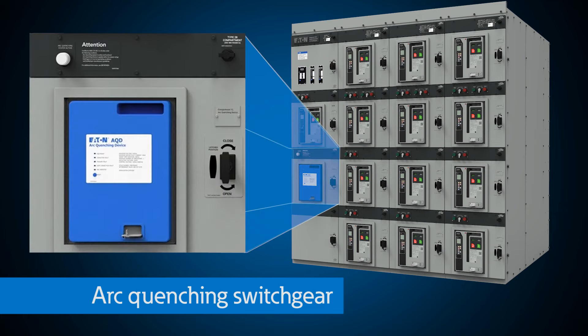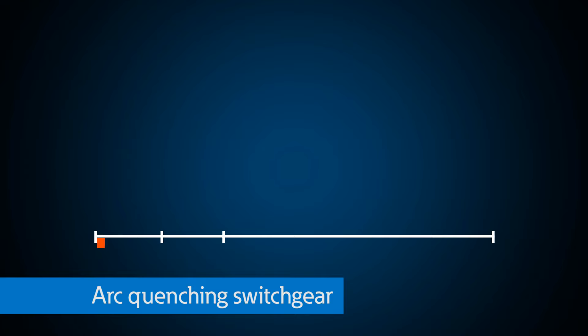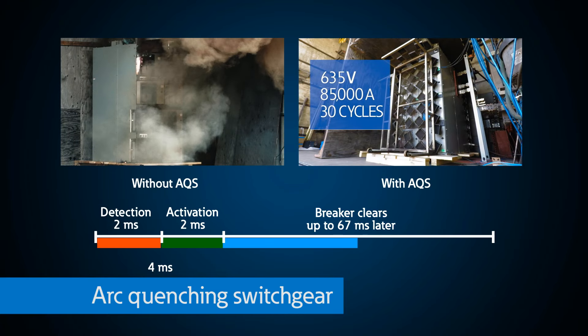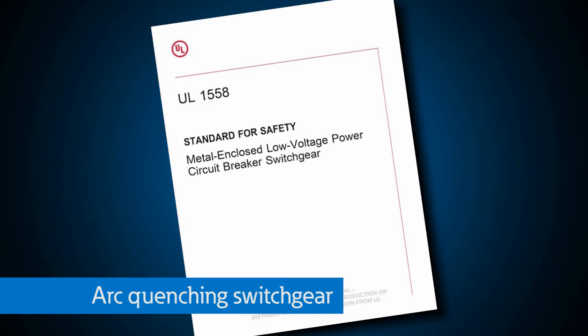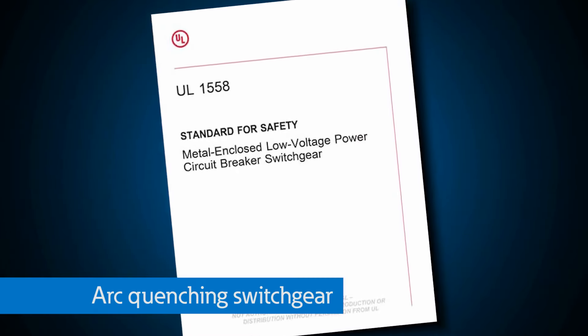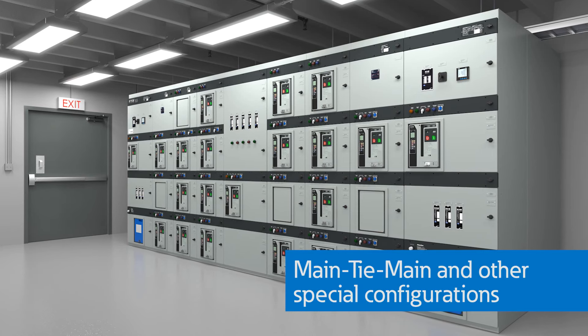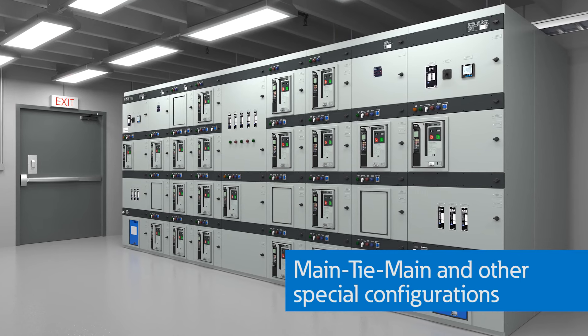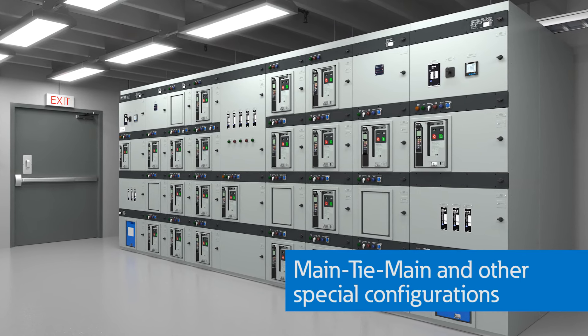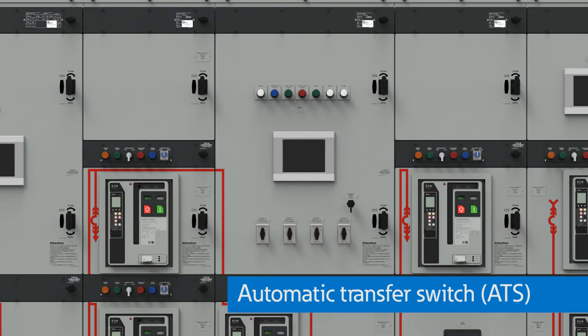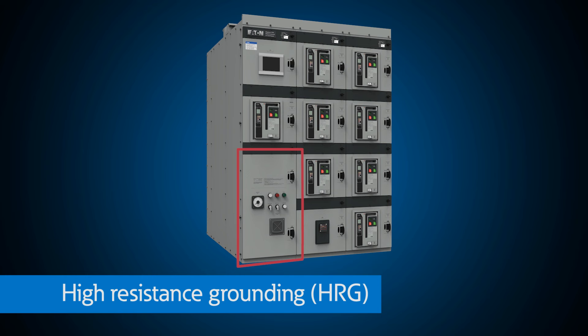Arc quenching switchgear reduces incident energy to a level where the switchgear will survive an electrical arc flash event while providing enhanced safety and minimal equipment downtime. Arc quenching switchgear meets and exceeds arc resistant testing requirements even when breakers are removed, doors are open, covers are removed, and without the need for ducts, plenums, or special enclosure construction. Other special configurations include main-tie main and other interlocks designed specifically for an application, which may include automatic transfer switches, high resistance grounding, and other special designs.